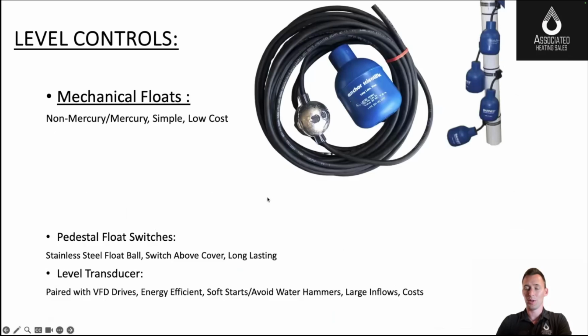Looking at controls real quick, the most common is our mechanical floats. They're strapped to a pipe, so they're either tethered to a pipe or suspended from the top of the pit. If your pit's really deep, suspended is usually the way to go because a long length of pipe is hard to get. So with a 15-foot deep pit, a 15-foot pipe is rather hard to install into this cover, so suspended becomes the option there. But anything standard, floor mounted, shallower basin, below 6 feet, sort of the tethered pipe mounted floats.